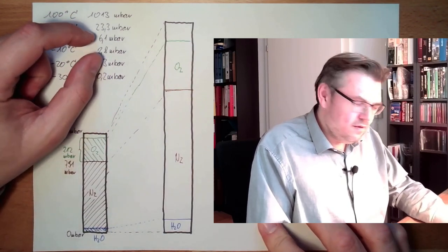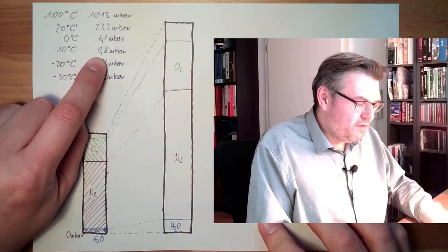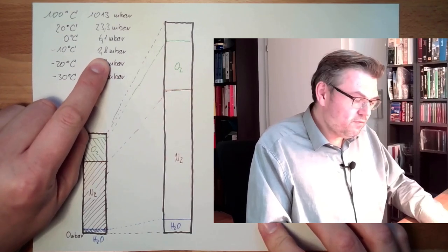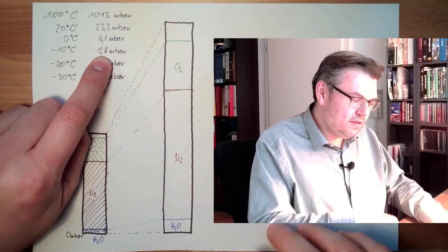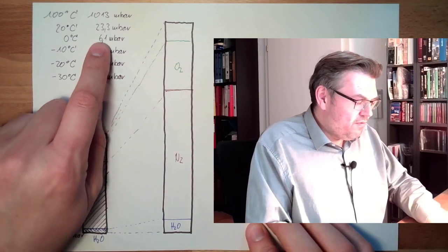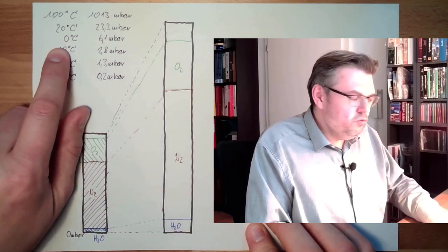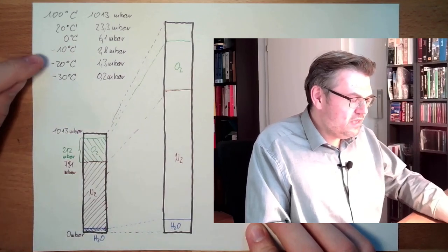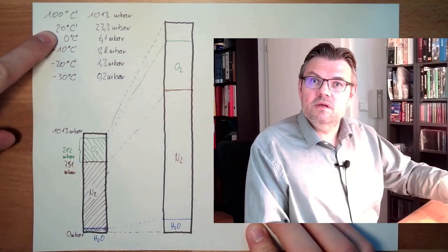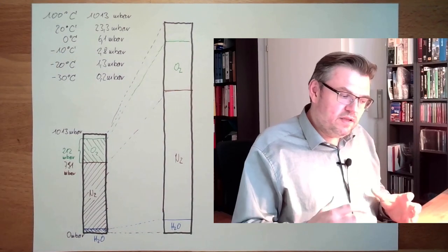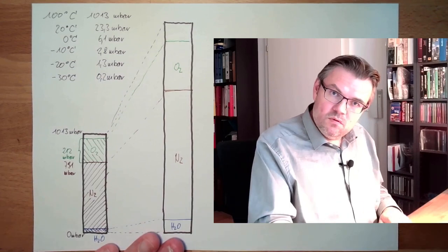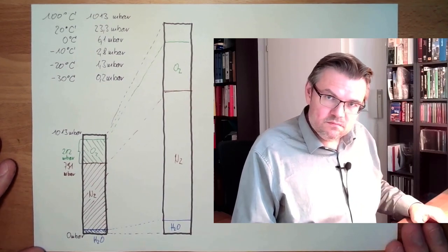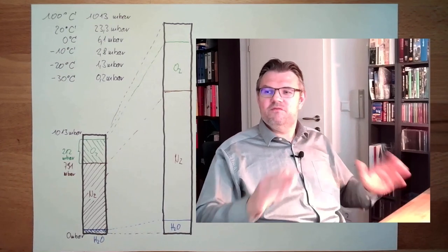If I then compress it, and now I double it, I don't have 2.8 millibar inside, I have 5.6 millibars, of course, because I doubled the pressure. Then 5.6 would be somewhere, let's say, minus 2 degrees Celsius. So the temperature where we start to condensate has been raised from minus 10 to minus 2 degrees Celsius. The more I'm compressing the air, the higher this Taupunkt will get. So I have to dry the air. That's the bottom line. I have to dry it.